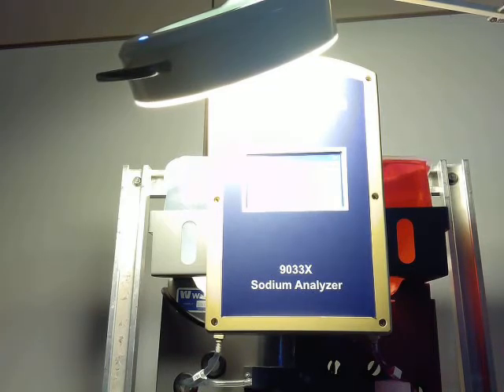Outside of that range that we have preset of 83 and 110, this just says, hey, we're far enough away from a theoretical passing calibration that something's probably not right. So again, with the calibration, it's all timing based. It's not looking for a certain number. It's saying, hey, analyzer, you have 10 minutes, 15 minutes to give me the number, the response that we need.